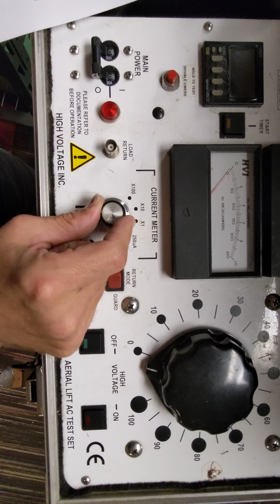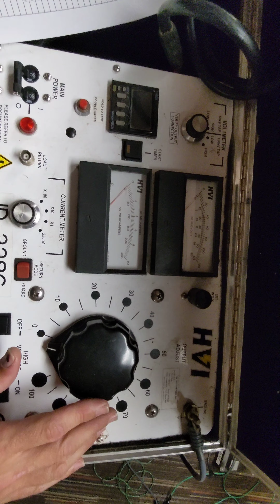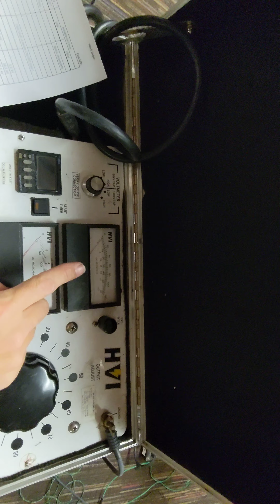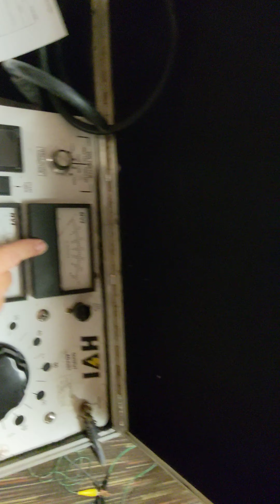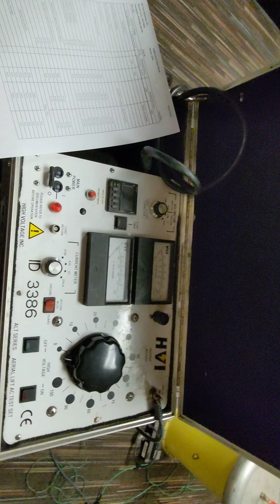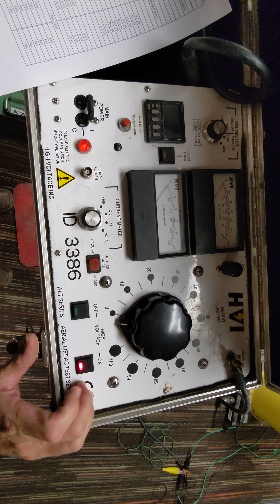So, we're set on our top tap. It doesn't matter whether you're on your low or high. You just need to know where your voltage is going to be coming from. Is it going to be coming from your side tap, or is it going to be coming from your top tap? We have it set on our top tap, so therefore we need it on either our low or high range of our 120 kV tap. We're not concerned as to whether or not it's ground or guard. It can be either, because we're not measuring any current leakage. And your current meter can be in any position, 250 microamps or times 1. Once again, we're not going to be measuring any current leakage, and so the current leakage is going to be very, very minimal.